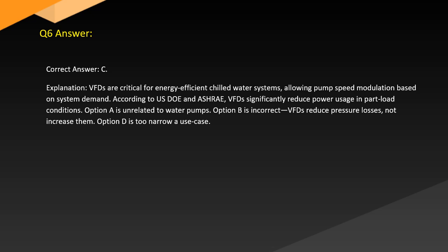Answer. Correct answer: C. Explanation: VFDs are critical for energy-efficient chilled water systems, allowing pump speed modulation based on system demand. According to ASHRAE, VFDs significantly reduce power usage in part load conditions. Option A is unrelated to water pumps. Option B is incorrect. VFDs reduce pressure losses, not increase them. Option D is too narrow a use case.